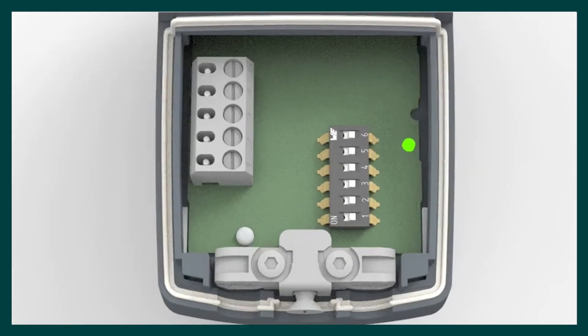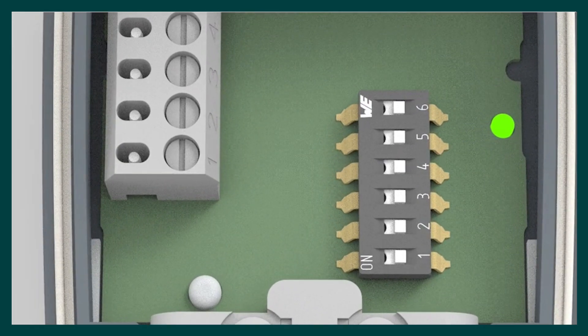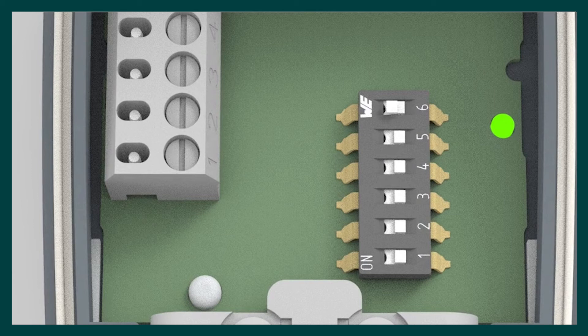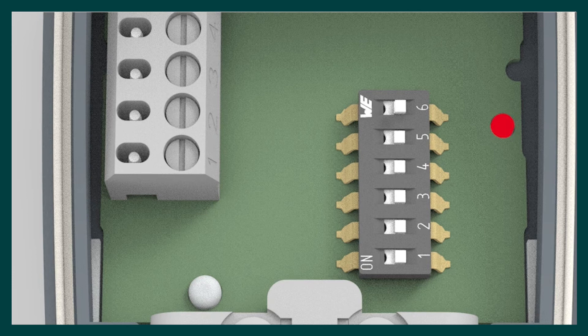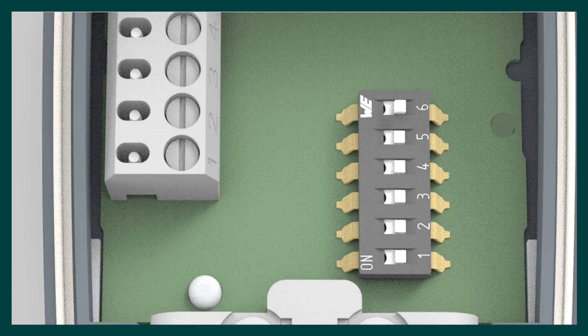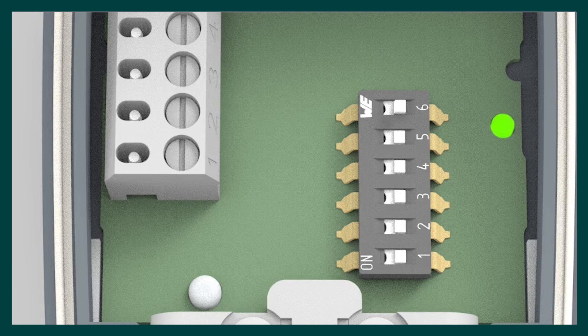To drive the actuator fully open, flip DIP switch 6 from the OFF position to the ON position, then back to the OFF position. The LED will now flash red and green. As well as driving the actuator open, this routine prepares the actuator for recalibration. The actuator will close with the LED flashing green. Once closed, the actuator will be recalibrated and the LED will be solid green.